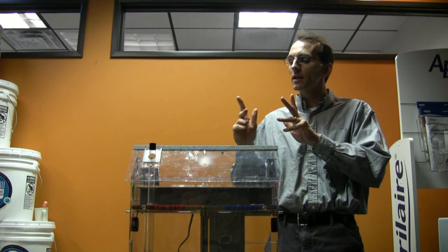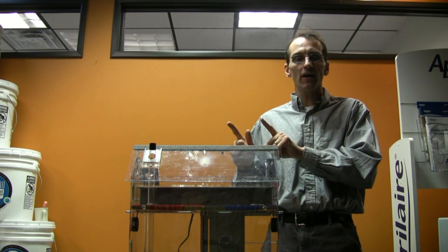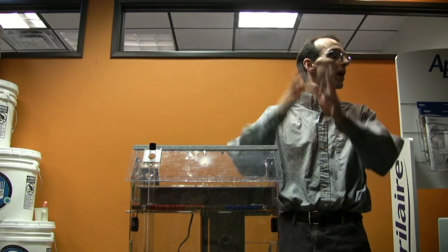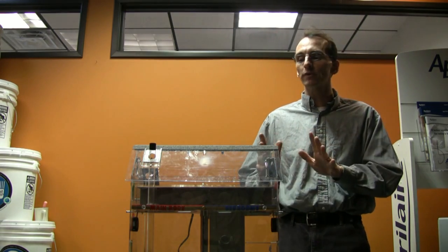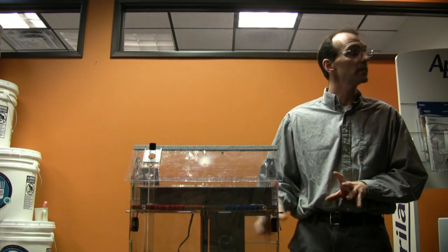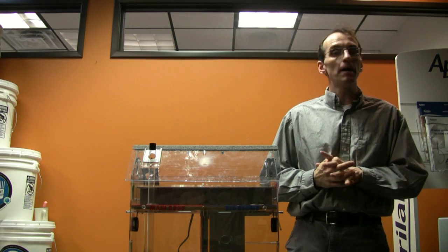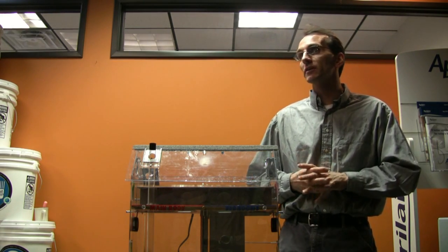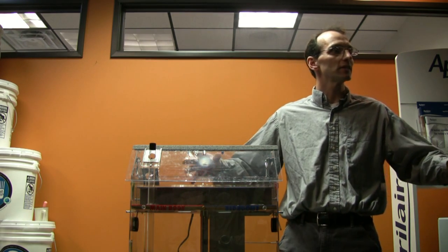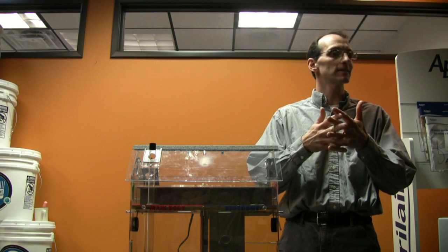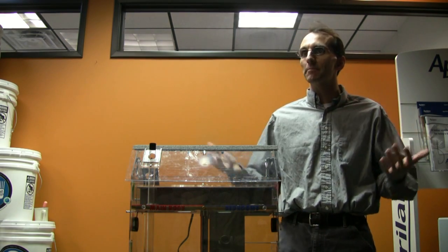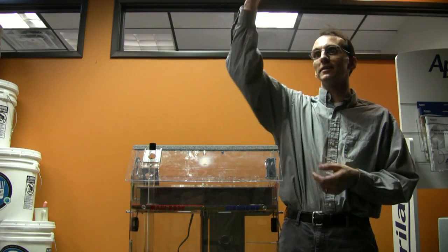Because that water heater now has to heat that whole flue up to be warm enough to get a good draw going. I'm just bringing this up because it's a related issue when you do combustion safety testing. I can't actually simulate that right here. You actually do a separate test that's called spillage. When you have a naturally vented appliance, you actually time how long the gases spill out into the room before the flue heats up enough that it creates a draw, and now the exhaust gases are leaving.